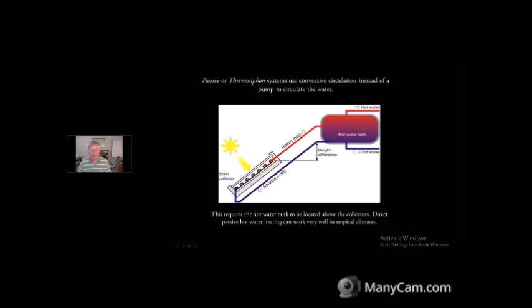These kinds of systems can work very well in tropical climates. What you're seeing here is also what's called a direct system, which we're going to get into in a minute, which basically means that we are running the hot water directly through the solar collector. So this is a very simple system, but it does require that you have the capability of physically supporting your hot water tank up high.